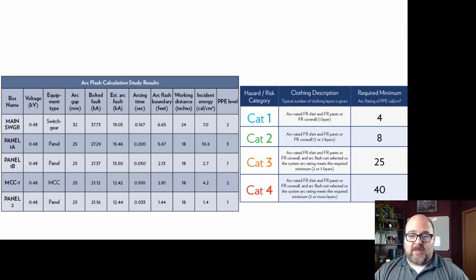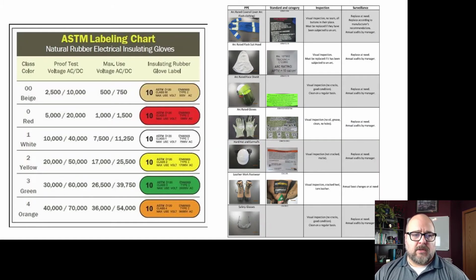On the right, we've got the four categories of hazard assessment, which dictate what PPE is required. It gives you the arc rating of the PPE in calories per centimeter squared—that's the incident energy level, and that's what finally dictates what must be worn. They also calculate other stuff, like energy in the arc and working distances, which all dictate the arc rating the PPE must withstand.